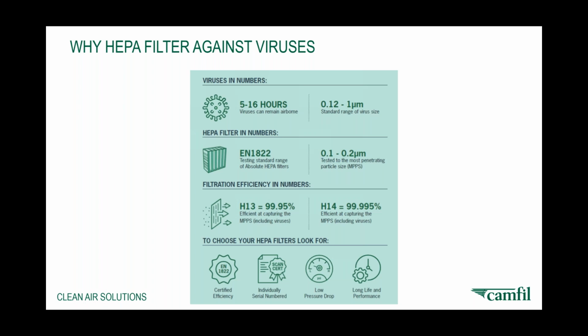So the efficiency of a HEPA filter against those viruses, and bear in mind that viruses typically travel on larger particles, so it'll be at least on the virus size or bigger. It'll get more efficient as the particles get bigger. A H13 HEPA filter would be 99.95% efficient at MPPS. That includes that virus size. And a H14, which we'll discuss in a second, 99.995% efficient. And that's a huge improvement on the standard ventilation filters that we discussed earlier on.